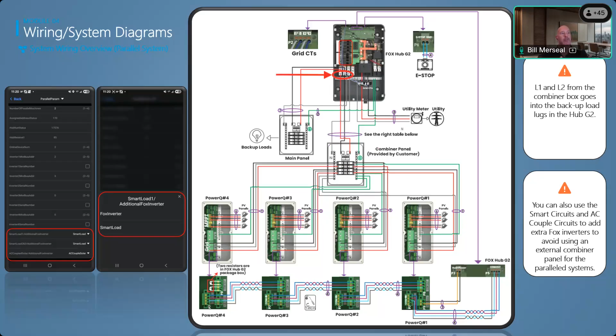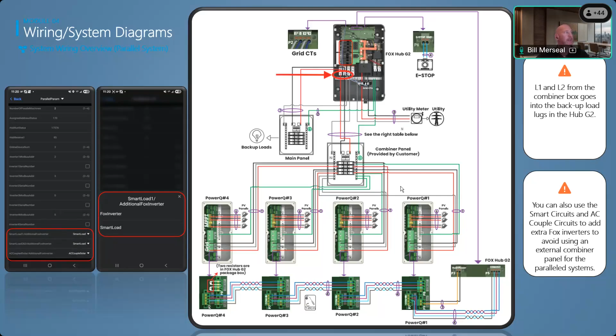By adding the ability to put these inside the hub itself, there's an AC solar location where you'd normally put your AC connections, and you have those 3 smart circuits on top of your hub. If you're not using those smart circuits or the AC connection, you can put the other inverter breakers in there. Then in the app, there's a parallel parameter on the hub you can change from smart load to Fox inverter. You just switch it there, and the system will know one of our inverters is inside one of those smart circuits or the extra AC combiner. We just launched that maybe 3 weeks ago, so we're excited about saving our installers even more money than before.